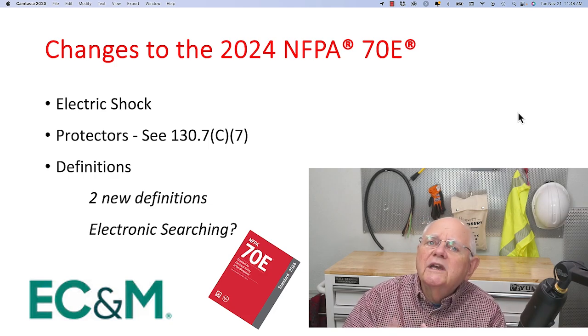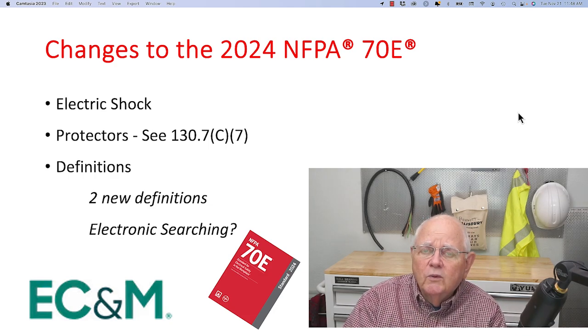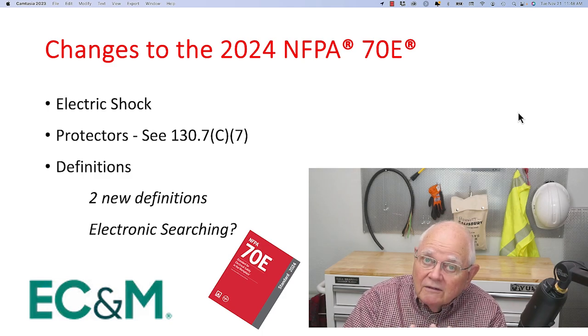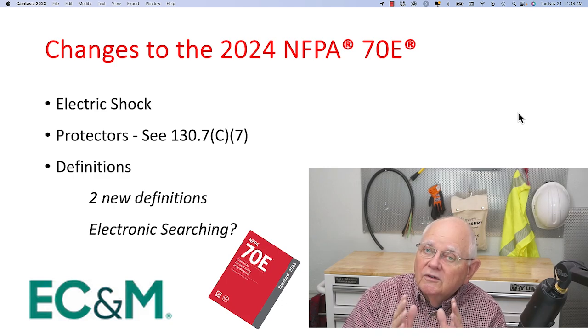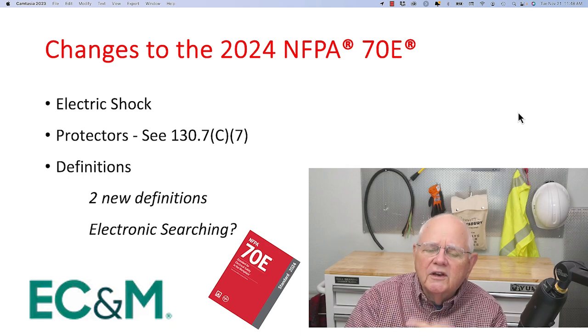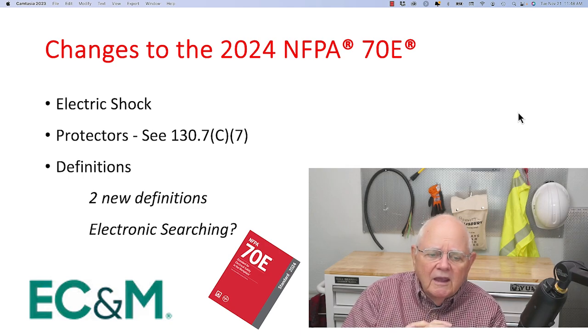So anyway, we can measure that corona effect. We can listen to that ultrasonic sound with the right type of test equipment. We call it partial discharge test equipment, and we do partial discharge testing. If you need more information on that, take a look at NFPA 70B. If you've got medium and high voltage, you have it. And if you're not maintaining your equipment properly, that corona effect can present you with some serious problems later on. It's an inefficiency in our systems as well.